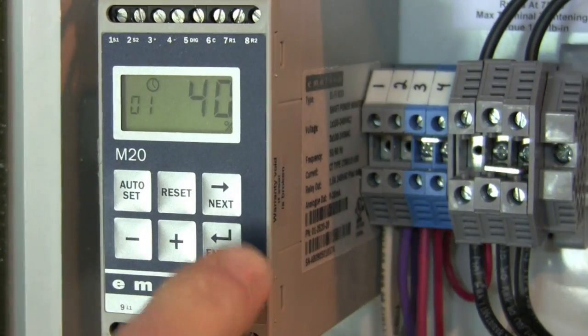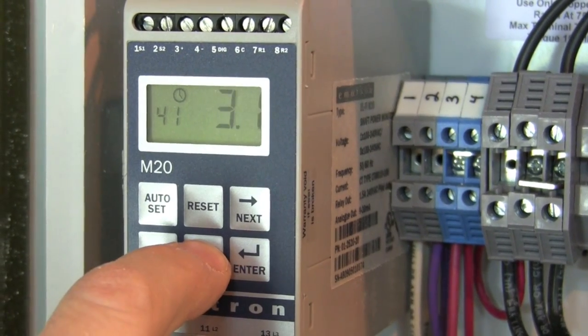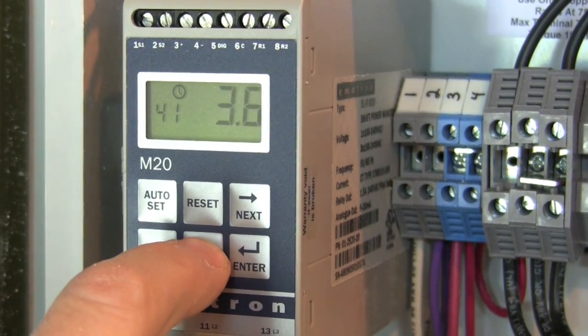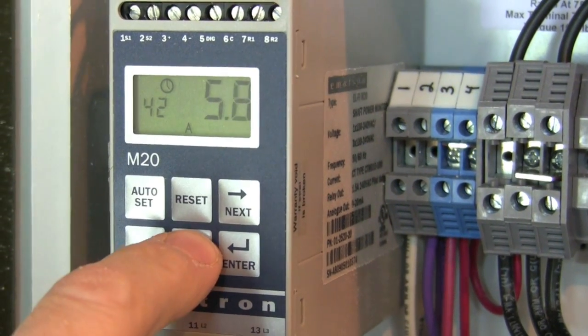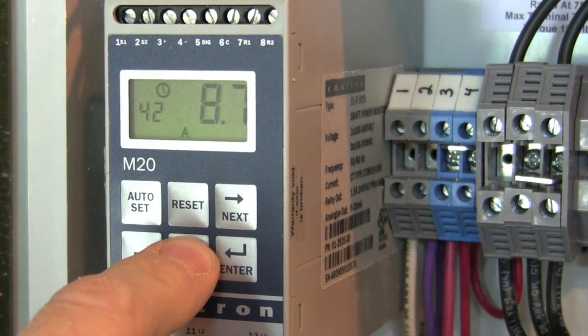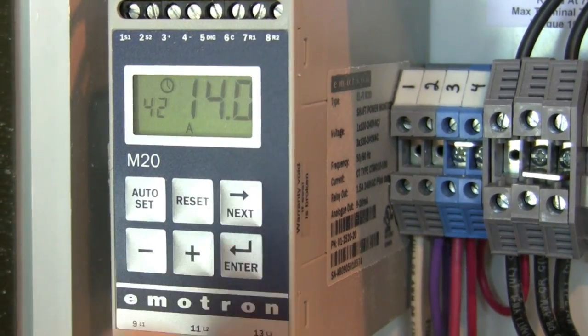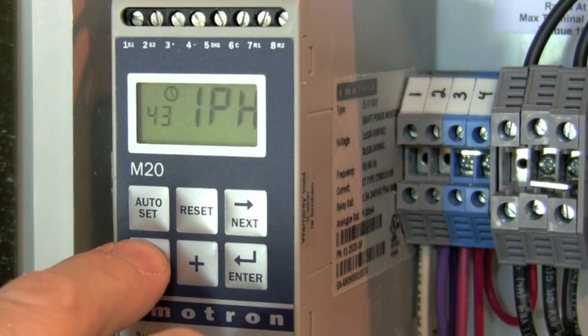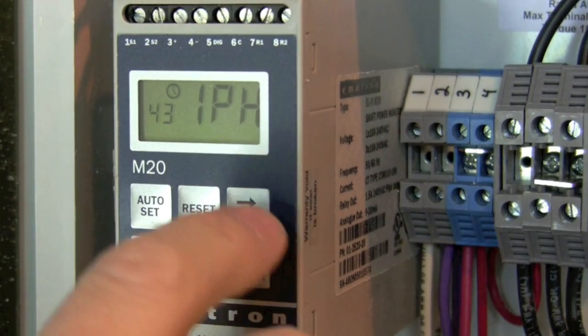Programming the M20 takes less than two minutes and involves just four steps. Press the next button until window 41 is shown. Press the plus or minus buttons to program the appropriate horsepower rating of the motor and press the enter button. Now go to window 42 using the next button, press the plus or minus buttons to program the motor's full load amps, and press the enter button. Go to window 43 and confirm that it displays the appropriate phase supply to the motor.